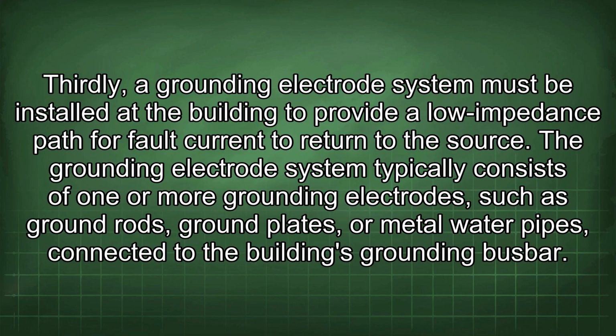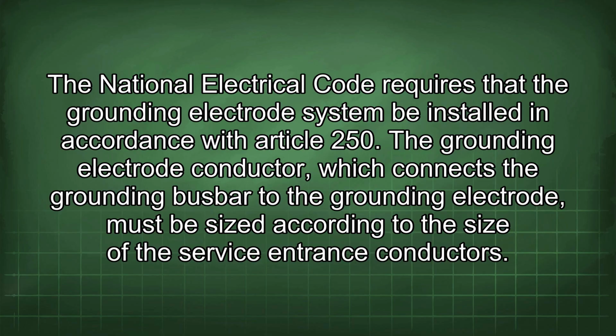Thirdly, a grounding electrode system must be installed at the building to provide a low impedance path for fault current to return to the source. The grounding electrode system typically consists of one or more grounding electrodes, such as ground rods, ground plates, or metal water pipes connected to the building's grounding busbar. The National Electrical Code requires that the grounding electrode system be installed in accordance with Article 250. The grounding electrode conductor, which connects the grounding busbar to the grounding electrode, must be sized according to the size of the service entrance conductors.